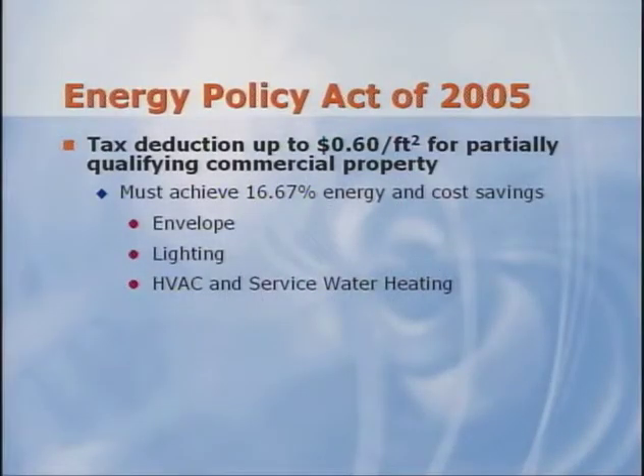Reaching the 50% energy and power cost savings marks will likely be difficult for many buildings, but keep in mind that partially qualifying tax deductions are also available for the envelope, lighting, service water heating, and HVAC systems. A building achieving 16 2/3% cost savings in any of these categories when compared to the standard 90.1 2001 reference building qualifies for a tax deduction of up to 60 cents per square foot.